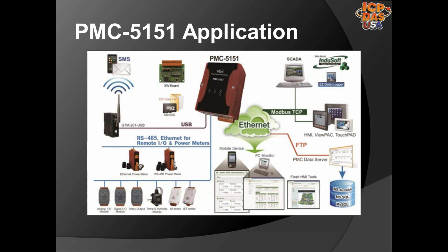PMC5151 and PMC5141 can be used with other Modbus devices and can trigger outputs based on inputs. They can log data from various devices and can send the data back over the cellular network with cellular modems. They support if, then, else type logic rules that are configurable through a web page, so you can trigger devices to turn on or off based on data acquired by power meters. PMC5151 comes with a 4 GB micro SD card and supports up to 24 devices.